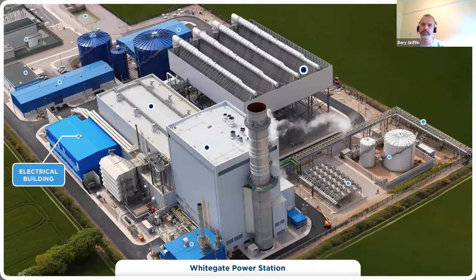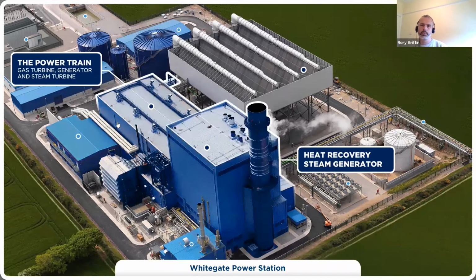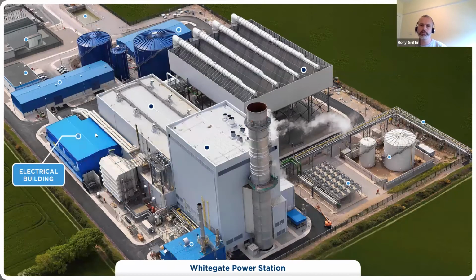This is the electrical building, so there are lots of pumps, motors, fans, etc. on the balance of plant. The balance of plant would be the term used for outside of the centre line. These are all supplied from the electrical building. The house supply is typically 1.5–2%. So, taking Whitegate as a 450 megawatt unit, its minimum stable level is 160 megawatts, so you're down around maybe 4 megawatts of house load. There's quite a lot of energy used at the site itself, mainly in the feed water pumps and the condensate extraction pumps. When the plant is up closer to maximum output, this house load increases to maybe 8, 9, 10 megawatts depending.